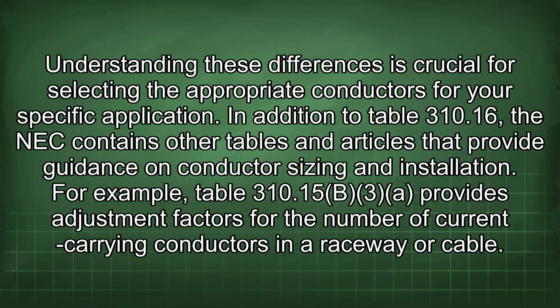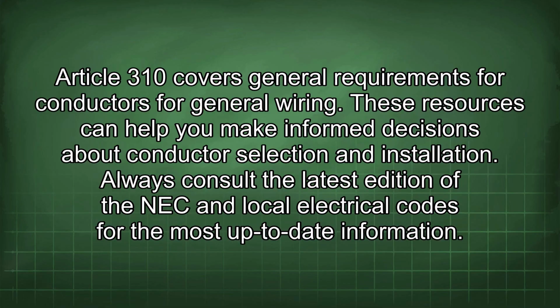For example, Table 310.15(B)(3) provides adjustment factors for the number of current-carrying conductors in a raceway or cable. Article 310 covers general requirements for conductors for general wiring. These resources can help you make informed decisions about conductor selection and installation. Always consult the latest edition of the NEC and local electrical codes for the most up-to-date information.